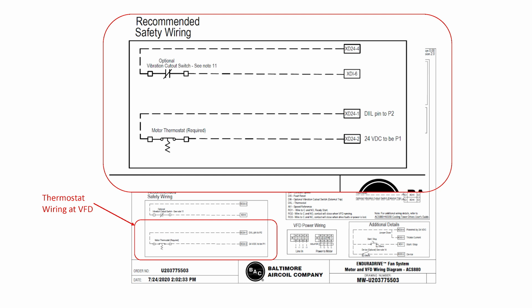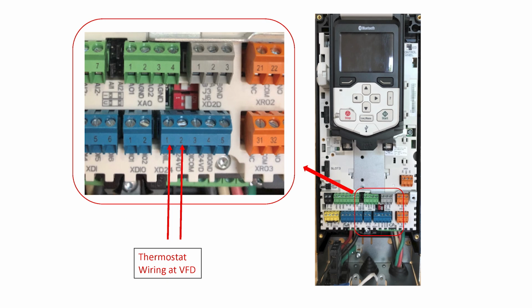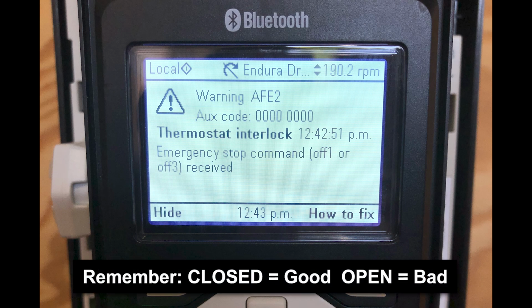Once you're sure the thermostat wires are connected at the motor, let's ensure they are connected at the VFD. Either one of the two wires needs to be connected to the terminal labeled XD24-1 and the other wire connected to the terminal labeled XD24-2. If the thermostat is not correctly wired, there will be a warning message on the display that reads Thermostat Interlock.